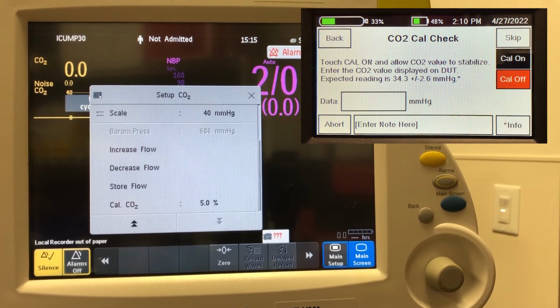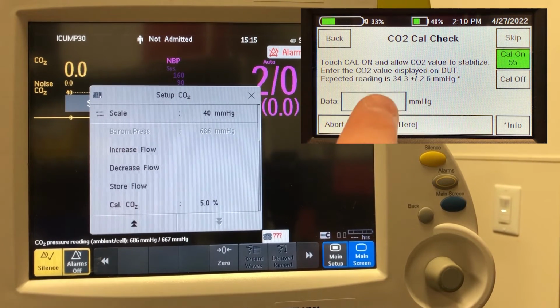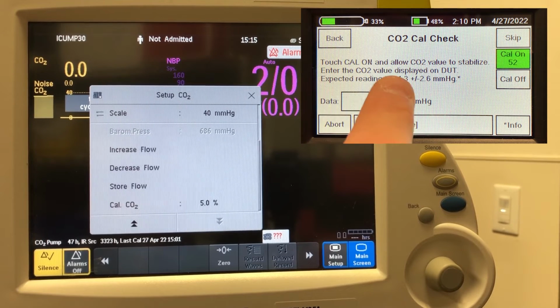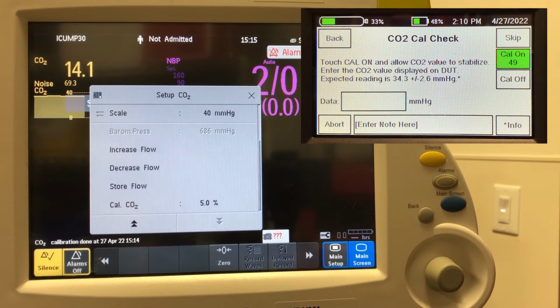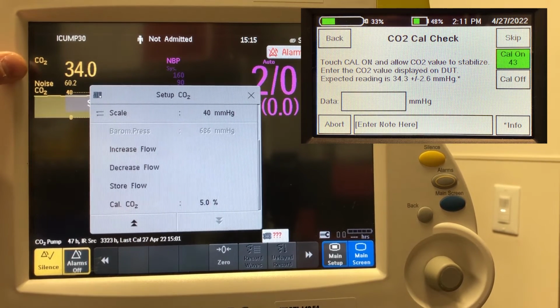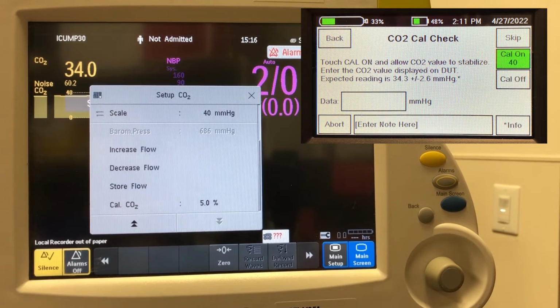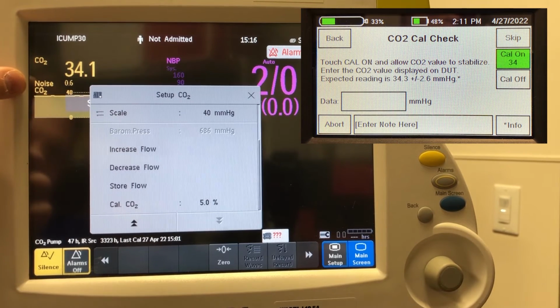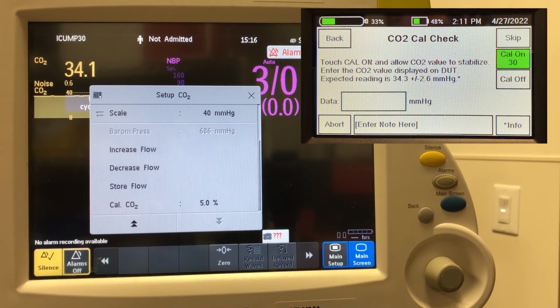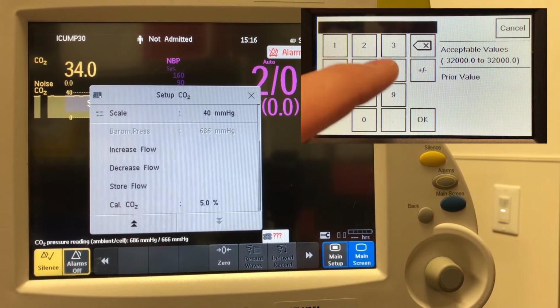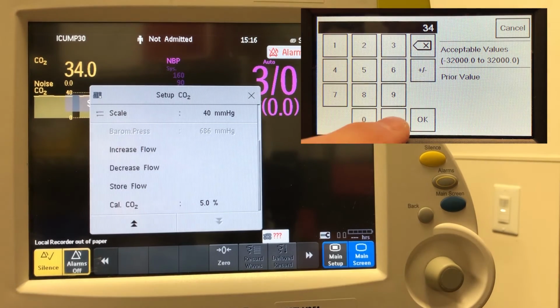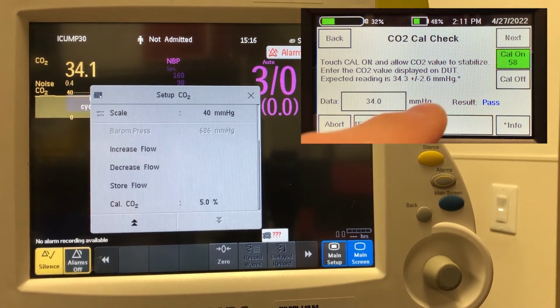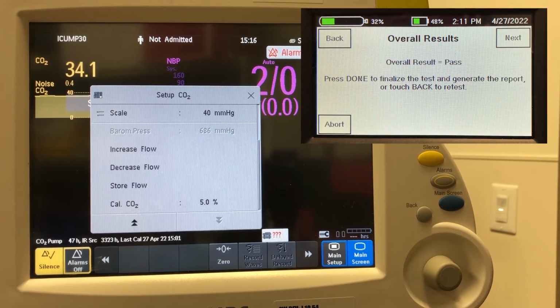And now we're going to feed calibration gas again and verify that the monitor up here reads what it should for this calibration gas and today's barometric pressure. So this 34.3 is calculated by the smart tank based on today's barometric pressure and the calibration gas that's in it. So we should expect this to read close to 34.3, plus or minus 2.6. We also want to look at this noise value and make sure that's less than 3 millimeters of mercury. So we can see that it's reading very close to expected value. We can turn cal gas off and move on. That's the end of this test.